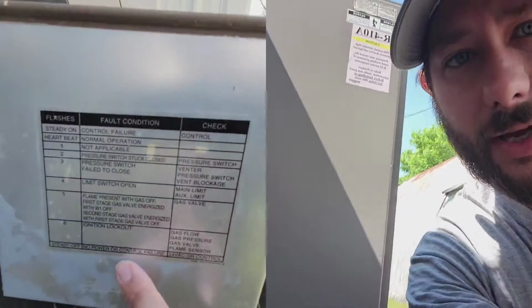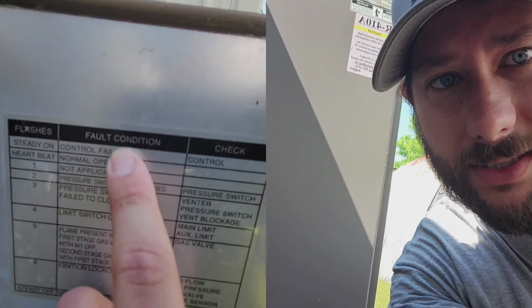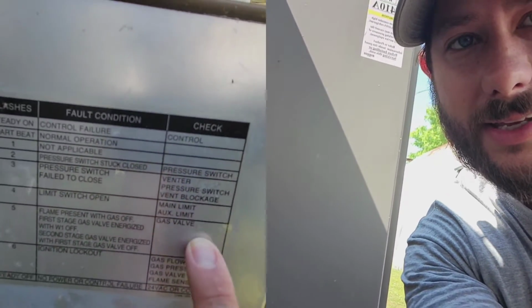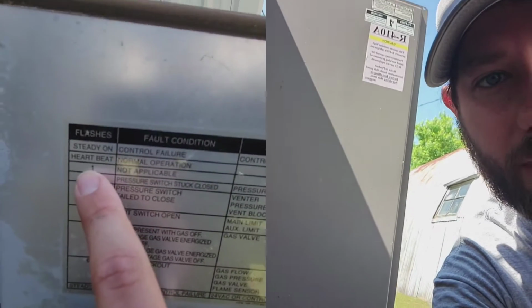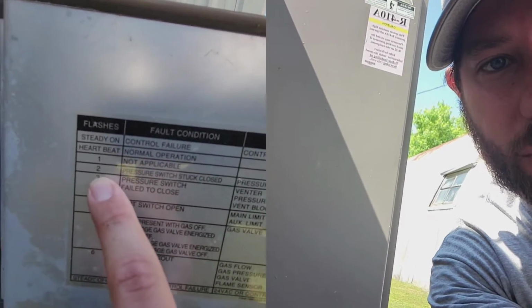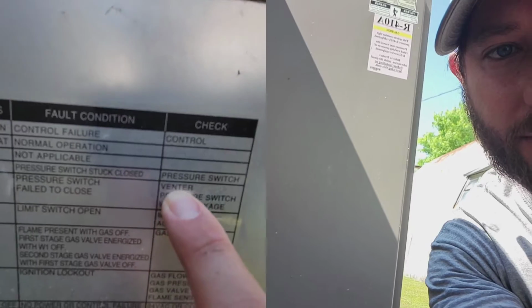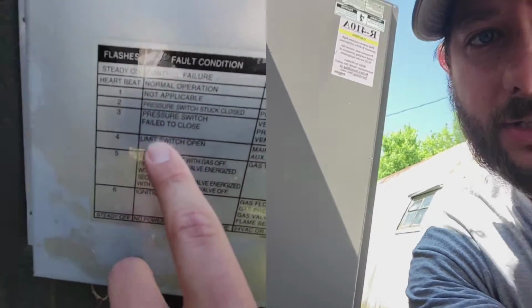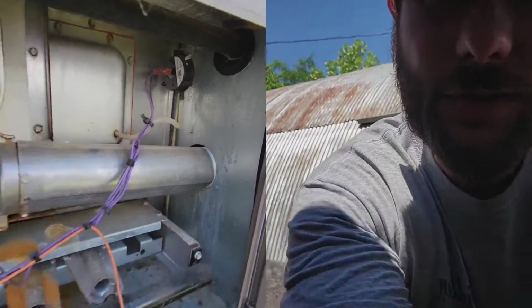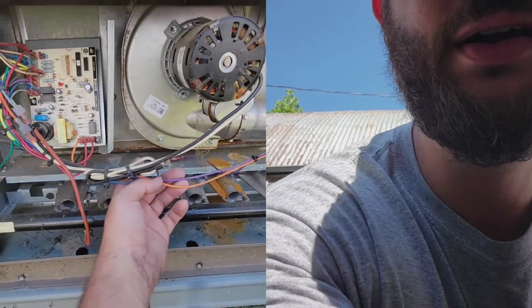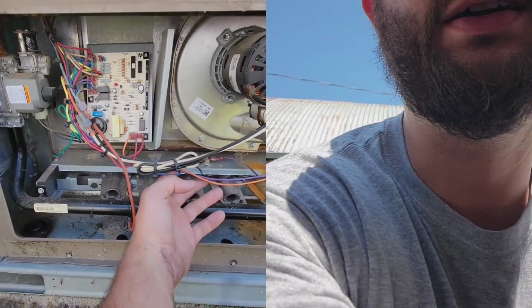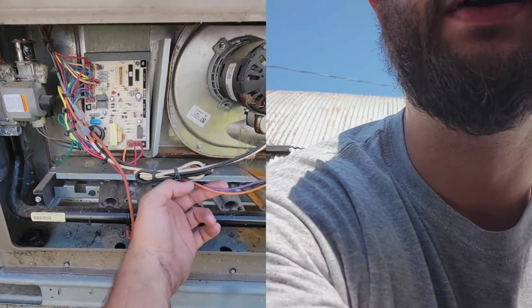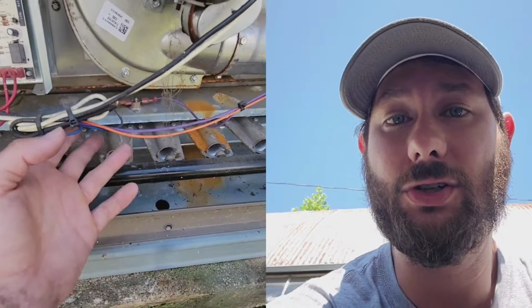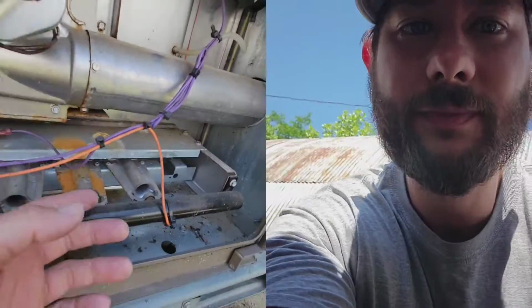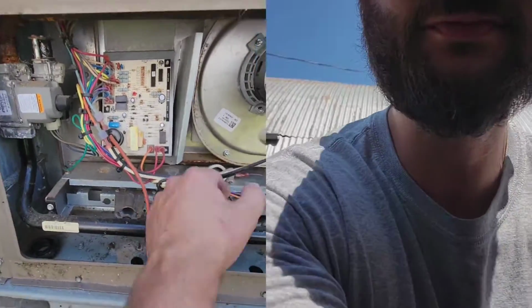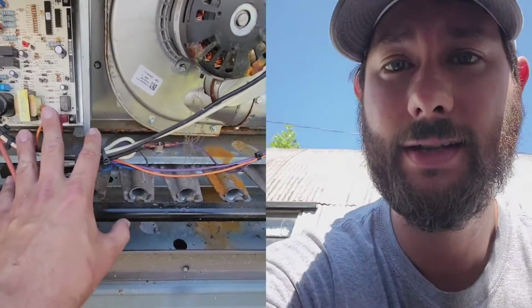But you've got this right here. Look at this. Fault condition. Check these. So number 2, if you have a steady heartbeat of 2 flashes, pressure switch stuck closed, check the pressure switch. And it's all 24 volts. So you got 24 volt controls. When you get into commercial units that are 460 and higher than that, then you've got maybe 120 volt controls, but these are 24 volt controls. So very, very simple. This is your gas heat section.